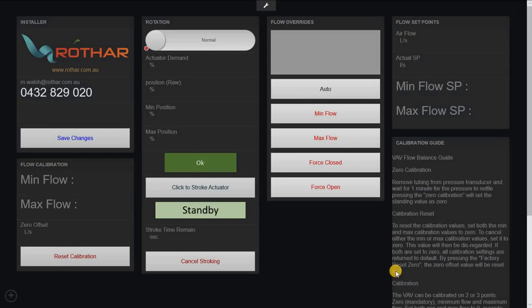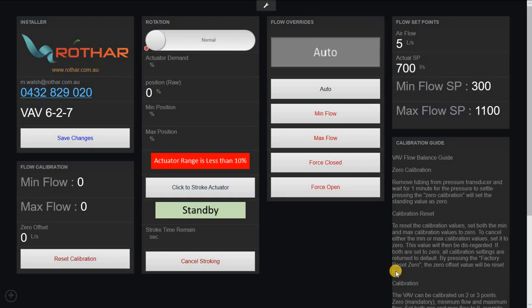We have a look at the flow settings page. This is where the flow balancing guys will come. This is the actuator. You can change the rotation of the actuator from here. You can see what its position is from a raw perspective, as well as its minimum and maximum positions as found during the stroke test, what the actuator is currently doing and how long it has to go.